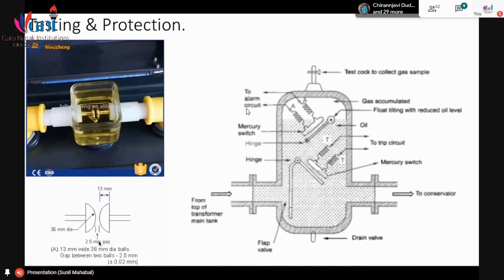So this is how the testing is done. It is done before monsoon and after monsoon. Before monsoon, because if the oil is already bad in dielectric strength, then during monsoon it will further deteriorate, and it may create problems for the working of the transformer. Therefore, it is done pre-monsoon, and post-monsoon it is done once again, because if moisture has gone inside the oil during monsoon, then it is better to check it so that for the rest of the year, the transformer will work without any problem.